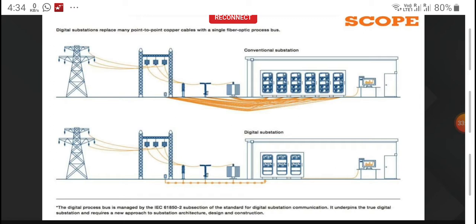so that the number of panels is going to reduce, and you can quickly identify any problems in the network, any problems in signal failures, any problems in the networking. Your control HMI will inform you where the problem is, what the problem is and the nature of the problem. Everything you will be notified through your control panel or your HMI. Through the HMI you can understand, so that the person will directly go to that particular problematic area and clear those problems.